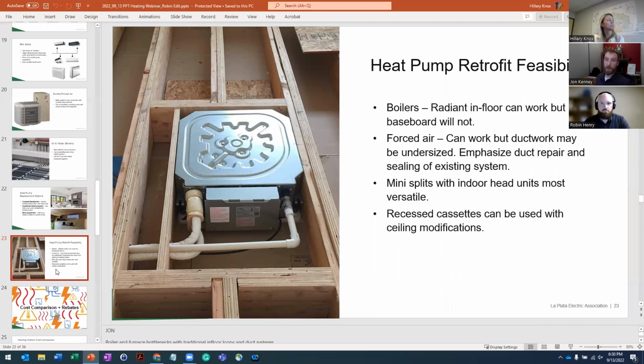Heat pump retrofit feasibility: a couple things to keep an eye out for when considering how a heat pump might work for your home and what you already have installed. With a boiler or radiant in-floor system, it can work, but the output temperature on the heat pump system maxes out around 130, where your existing system may be designed for 150 or 160. So really get in contact with a contractor to find out exactly what's in place and whether a heat pump will work for it.